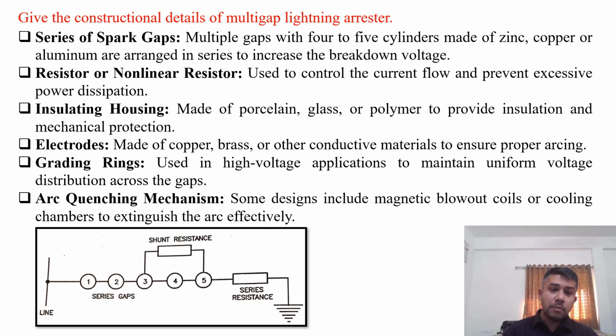Insulating housing made up of porcelain, glass or polymer to provide insulation and mechanical protection. Electrodes. These electrodes are made up of copper, brass or other conductive materials to ensure proper arcing. Grading rings used in high voltage applications to maintain uniform voltage distribution across the gaps. Arc quenching mechanism. Some designs include magnetic blowout coil or cooling chambers to extinguish the arc effectively.